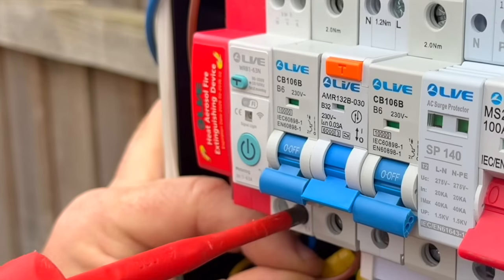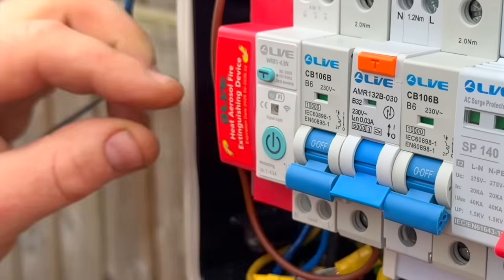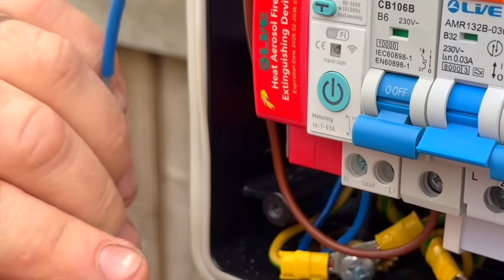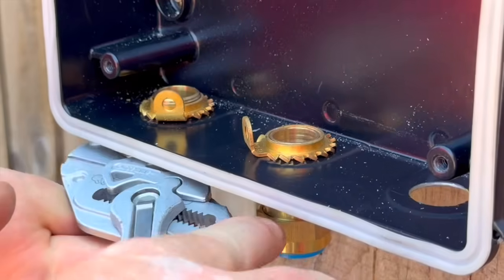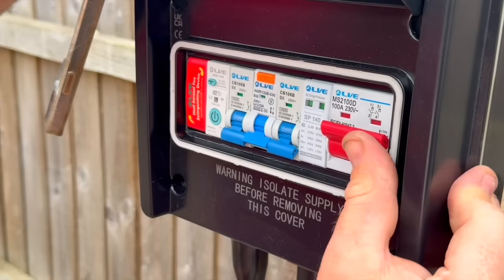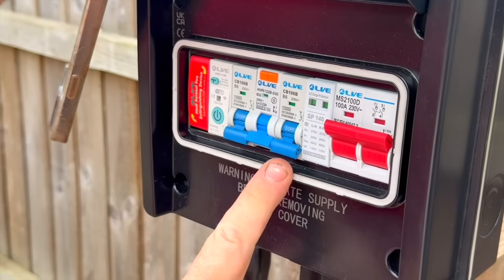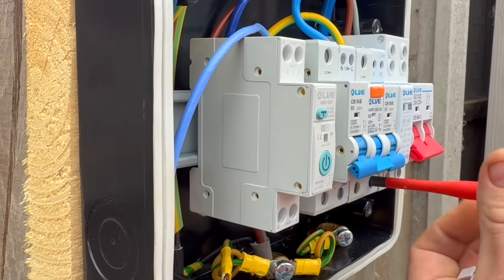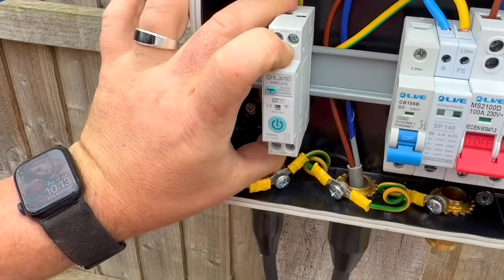There is also an important installation point. The Wi-Fi circuit breaker switch is installed within the board, but it is not something you install inside another manufacturer's board. A consumer unit is a type tested assembly. The enclosure, bus bar system, protective devices, and associated components are tested as a combination. So this device can be installed inside a Live Electrical board.